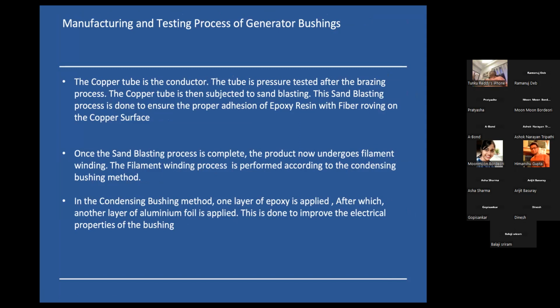In the filament winding process, apart from the regular filament winding, we do the condenser bushing method. In the condenser bushing method, the difference is we apply one layer of epoxy, after which we apply another layer of aluminum foil. Now, why is this done? It's usually done to improve the electrical properties of the bushing.